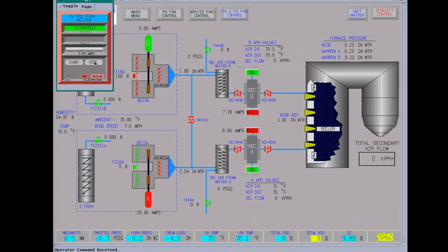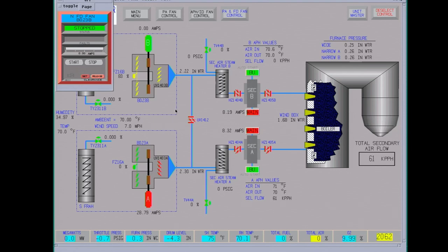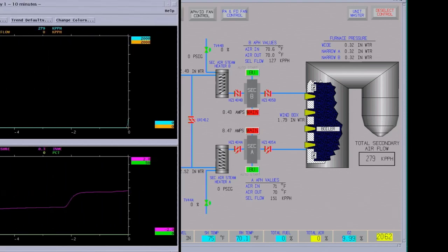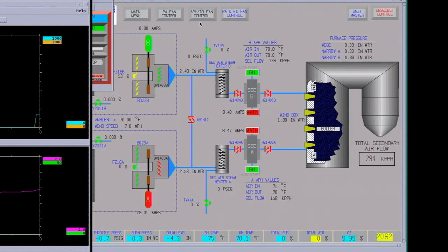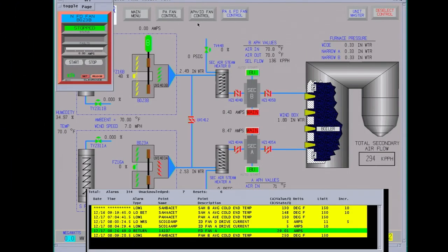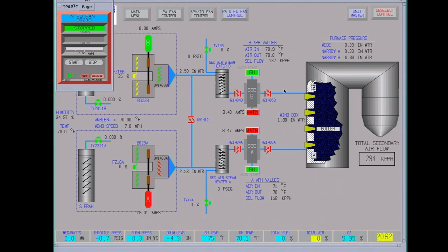Do the same and start the B. Once again, you'd announce on the plant, you'd have somebody out there. You can see our furnace pressure went slightly positive, we'll probably have to adjust it if it doesn't grab control of it. So this air here is feeding the burners in the boiler. Your primary air feed pushes the coal into the boiler through the pulverizers.